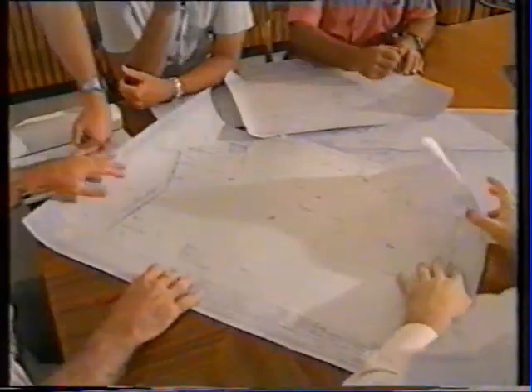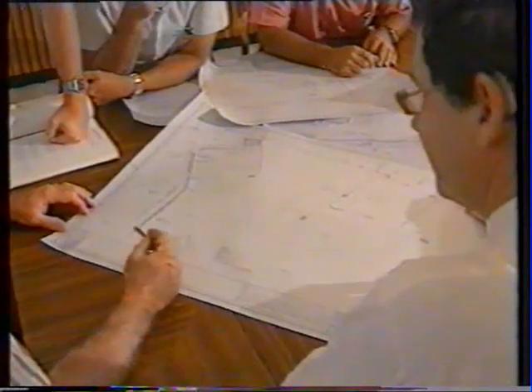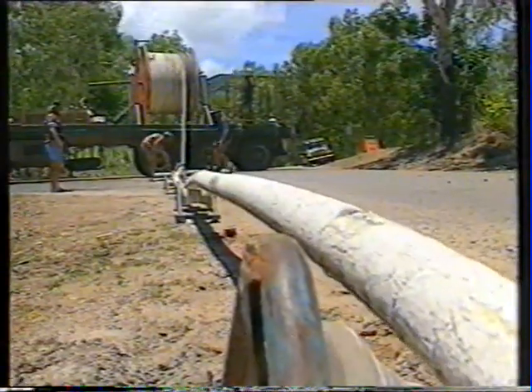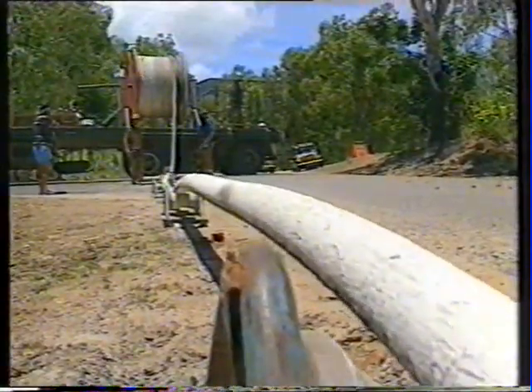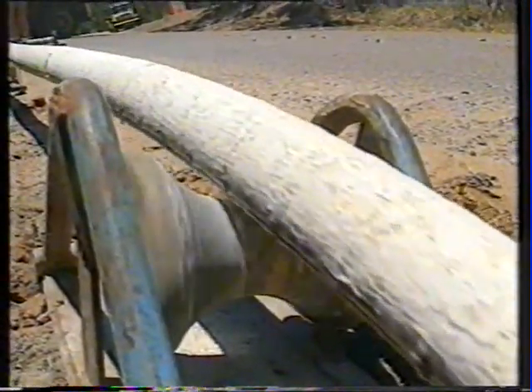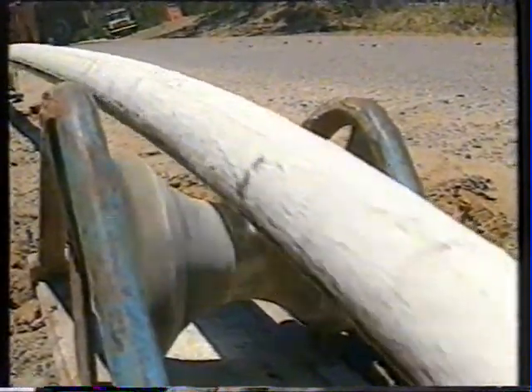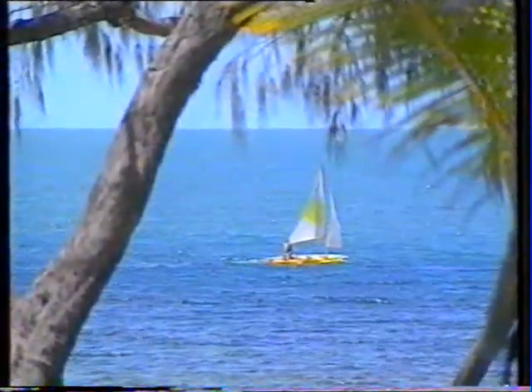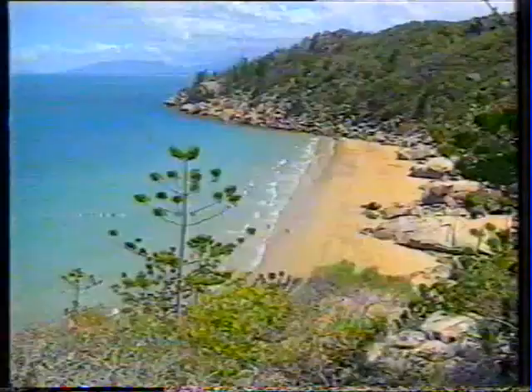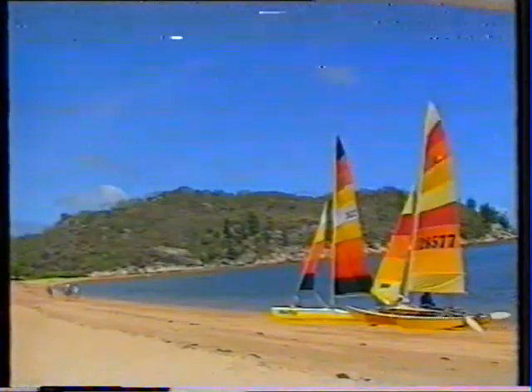The new cable will initially be energised at 11,000 volts, being the standard distribution voltage of the region. However, the option is available in the future to energise this cable at 22,000 volts in order to double the capacity on the cable. Magnetic Island has a permanent residential population of 2,000 people, the majority of whom reside in the 4 main bays at the southern end of the island. Development in these bays is residential, with a small amount of light industrial and commercial premises. In addition to the benefits of a regular supply of electricity from the mainland, the island also receives town water and telephone services.